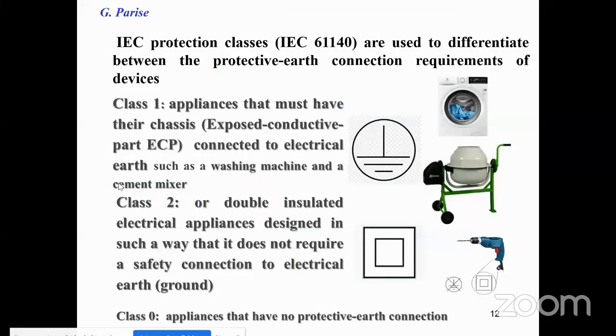IEC protection is very important to give another very important definition. And so it's important to highlight how the IEC differentiates between the protective earth connection requirement of the devices. So there exist class 1 appliances that must have their chassis exposed conductive part connected to electrical earth, such as a washing machine and a cement mixer, as shown in the slide.